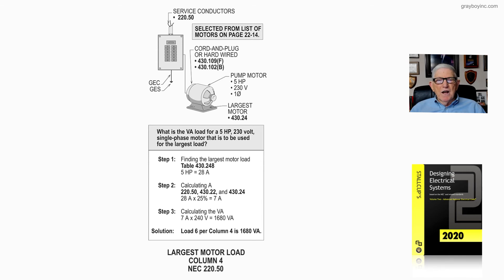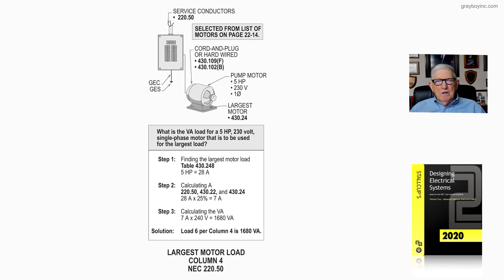We take 25% of the largest motor, which was 28 amps — selected from that list on page 22-14. When we do the math, 25% of 28 amps, we come up with 7 amps.